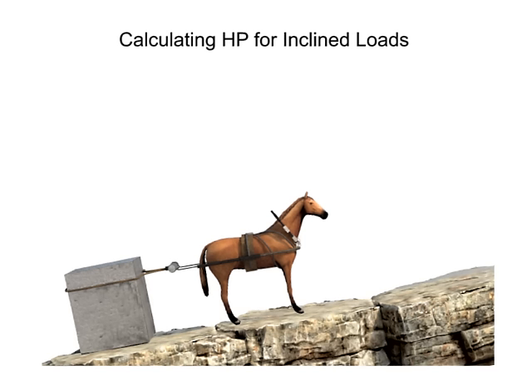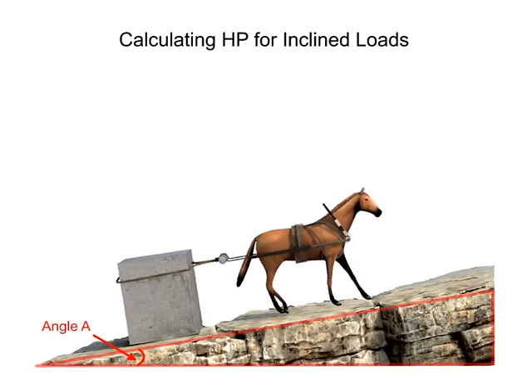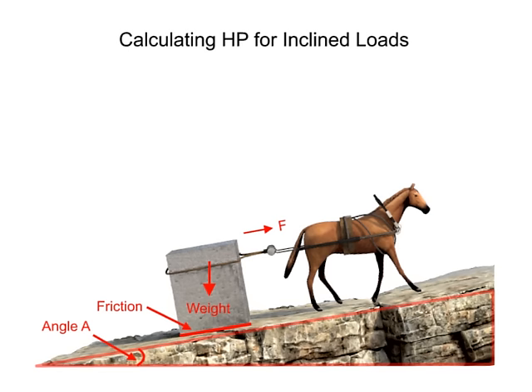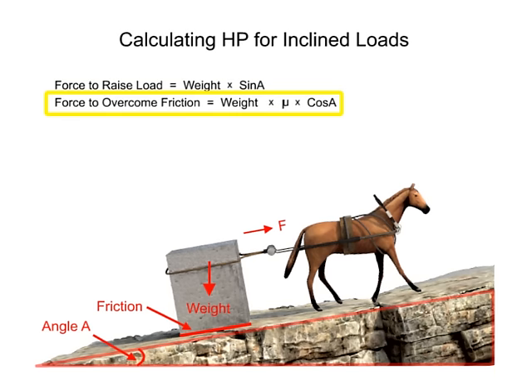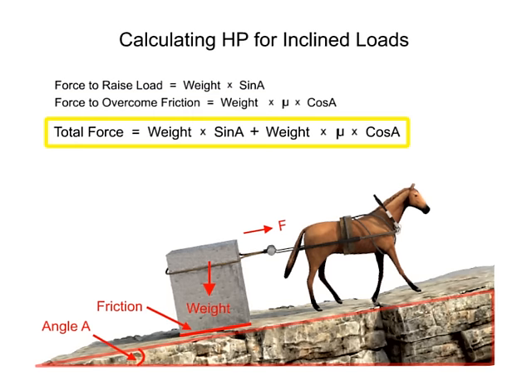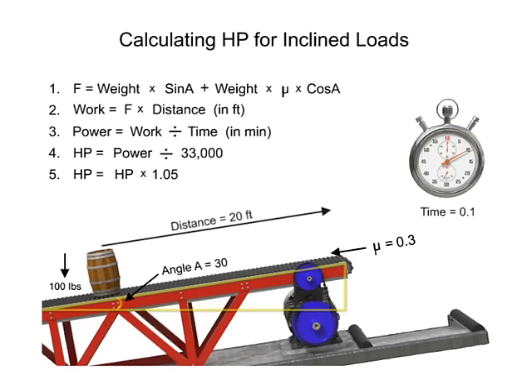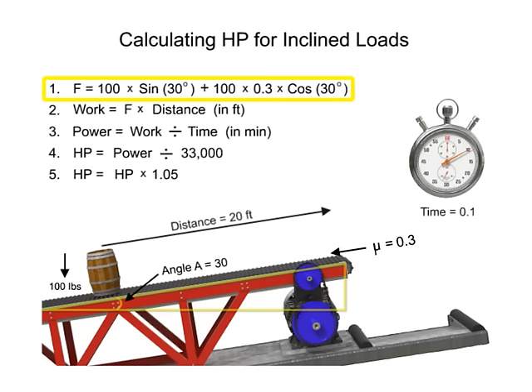If the distance to be traveled isn't on a horizontal surface, the angle of the surface must be taken into account. To determine the total force required, we must add the force required to raise the load to a higher elevation with the force required to overcome the friction. The total force is equal to: weight × sine A, plus weight × coefficient of friction × cosine A. Once these two forces are combined, we can continue with the same steps used previously to calculate the size of the motor required. In this system, the total force is 75.98 pounds.